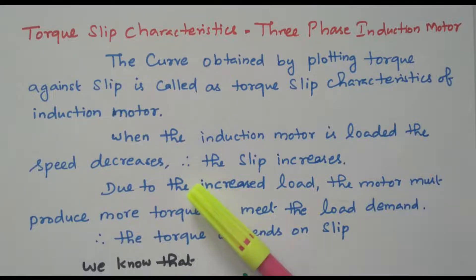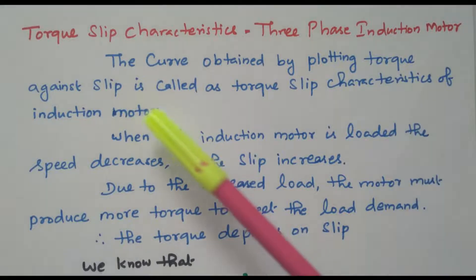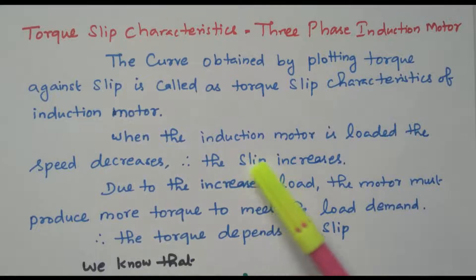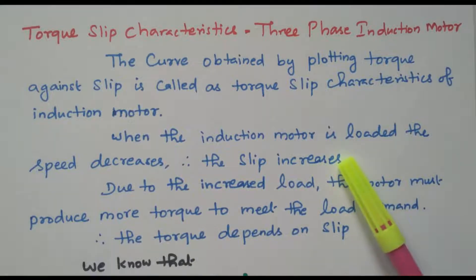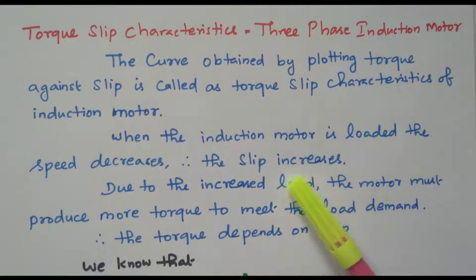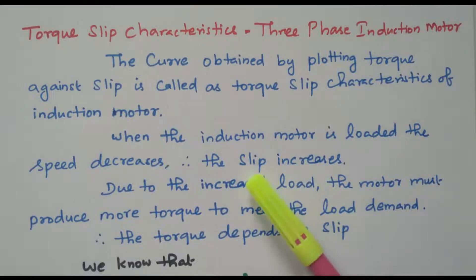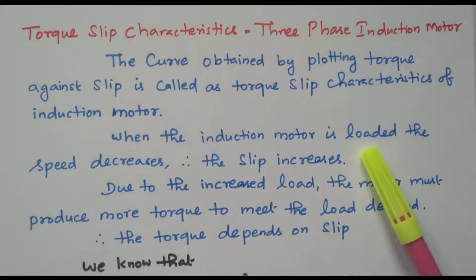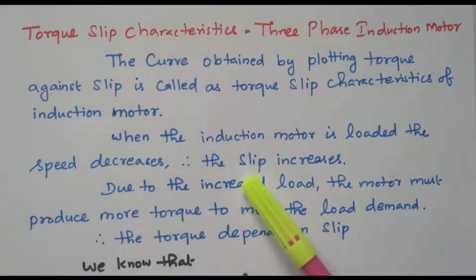Now we will see the details about the relation between torque and slip. When the induction motor is loaded, the speed decreases, therefore the slip increases. Slip is nothing but the difference in speed between the actual speed and synchronous speed. So when the motor is loaded, the actual speed decreases, creating a difference from synchronous speed, which is why slip also increases.